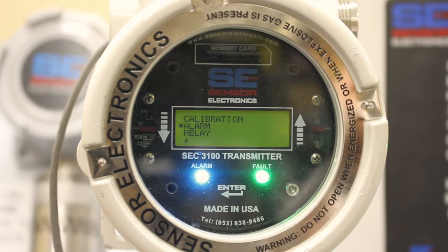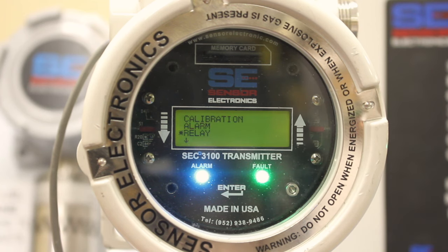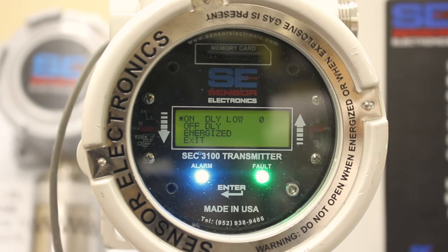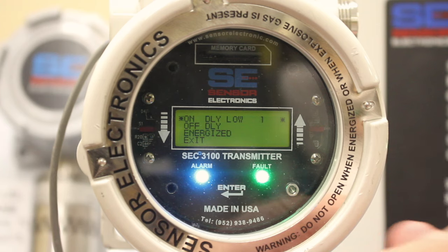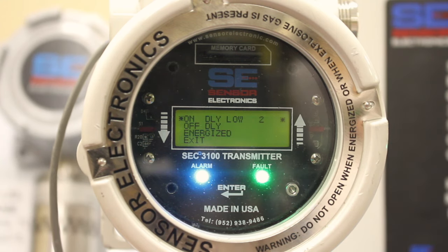And then the next menu is what we call Relay. And here we can set in time delays in the relay. We can set an on delay time so that it's measured in seconds. So if we wanted to have the alarm come on after a certain amount of seconds that the gas is sensed, we can program in that time delay into this menu. So right now it'd be set for 2 seconds. So once the sensor went above that 11% LEL and stayed there for 2 seconds, then the relay would turn on.